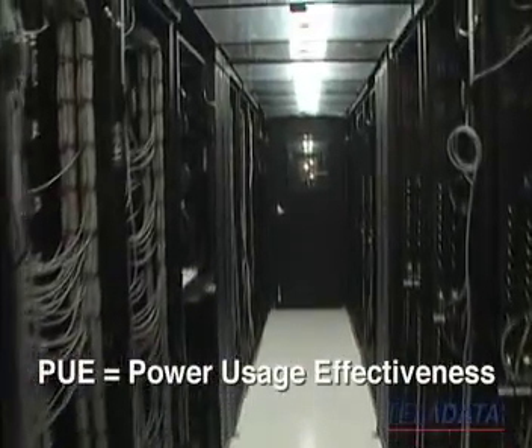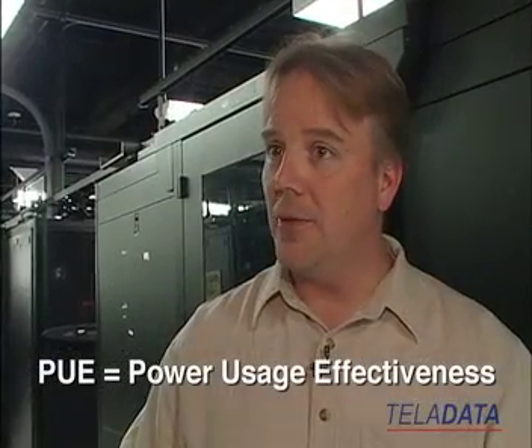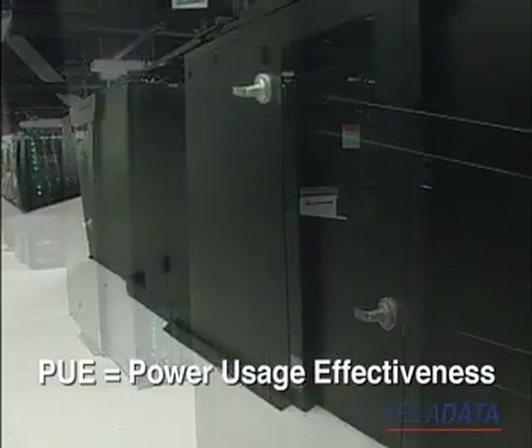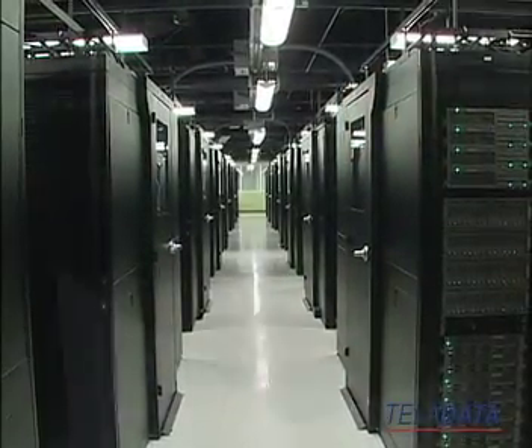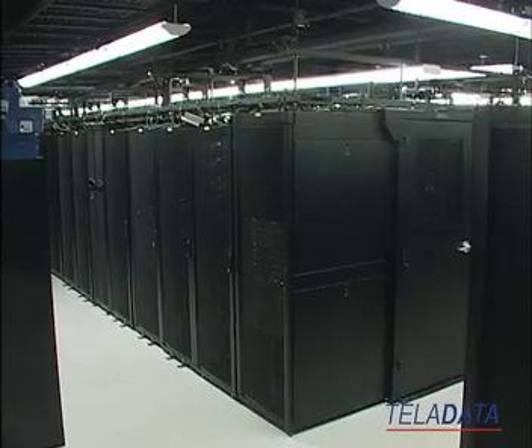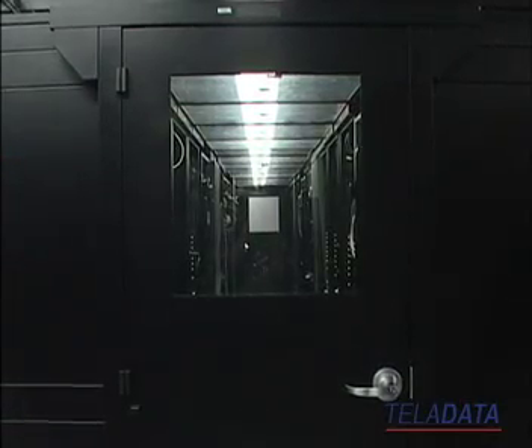The PUE of this data center is 1.28, which means that 78% of the actual power is going into the actual IT load. You've been telling me that you've been gradually raising the temperature. Where are you at now? So we're at 74 degrees inlet to all of these different pods. And then inside of the hot aisle itself, we'll go take a look at that in a sec, it's between 95 to 105 degrees. Yeah, no, the whole point is that you're isolating the heat. And when you do that, you can run the data center a lot warmer. And every degree that you increase the temperature in a data center, every Fahrenheit, is a 4% efficiency gain all the way through to the plant.